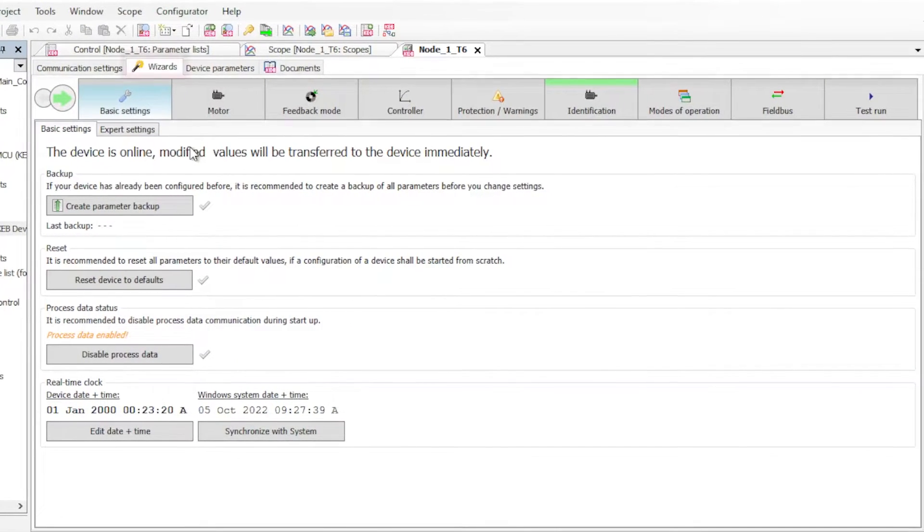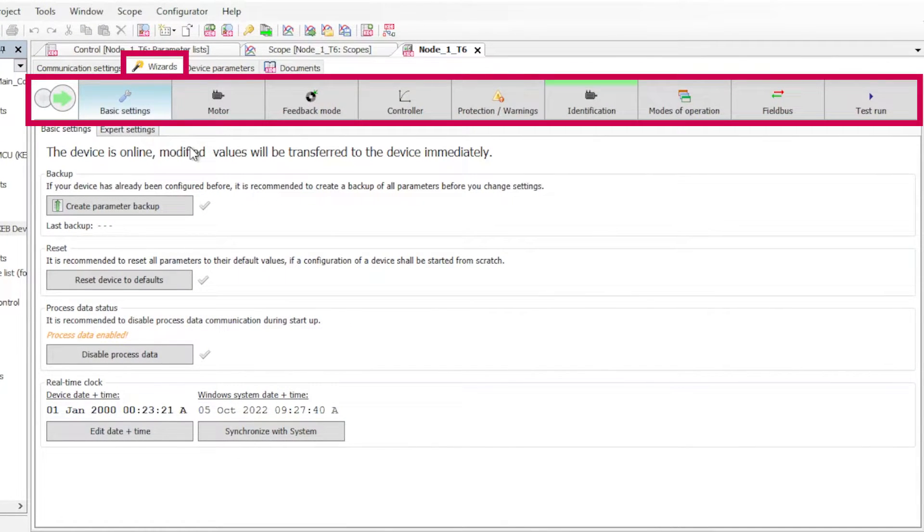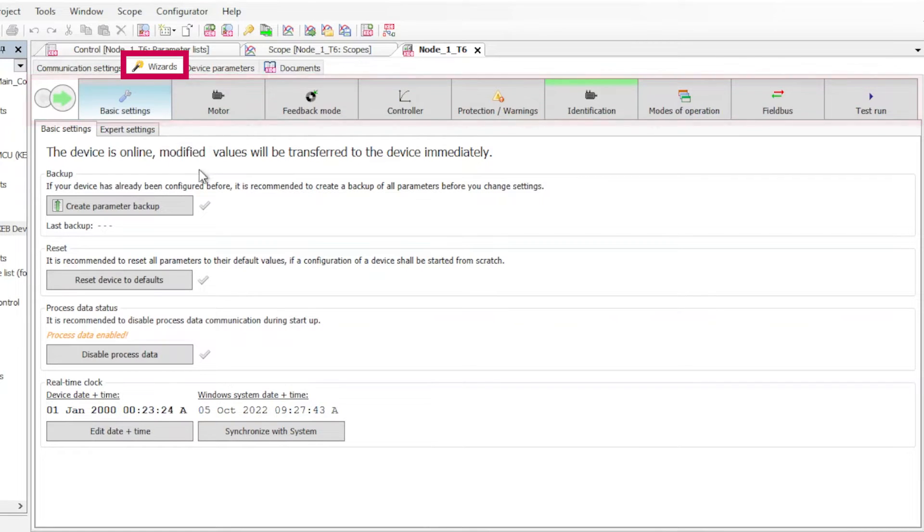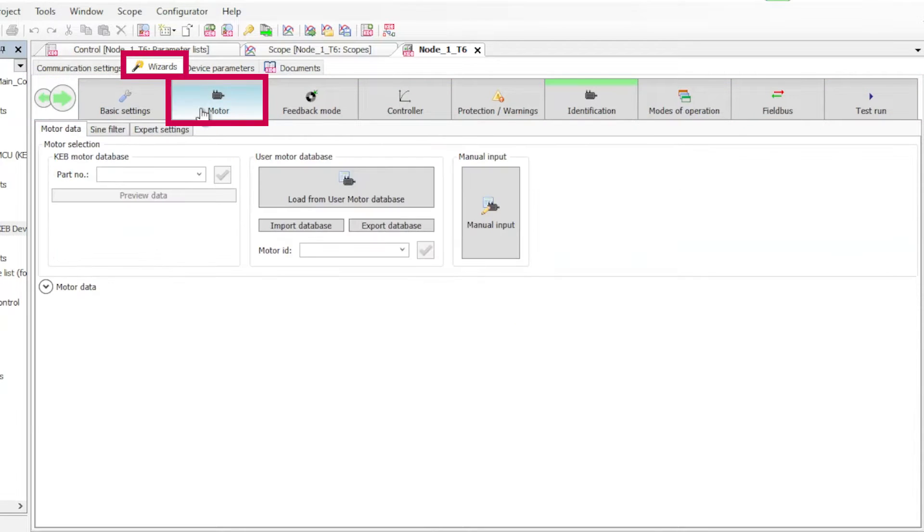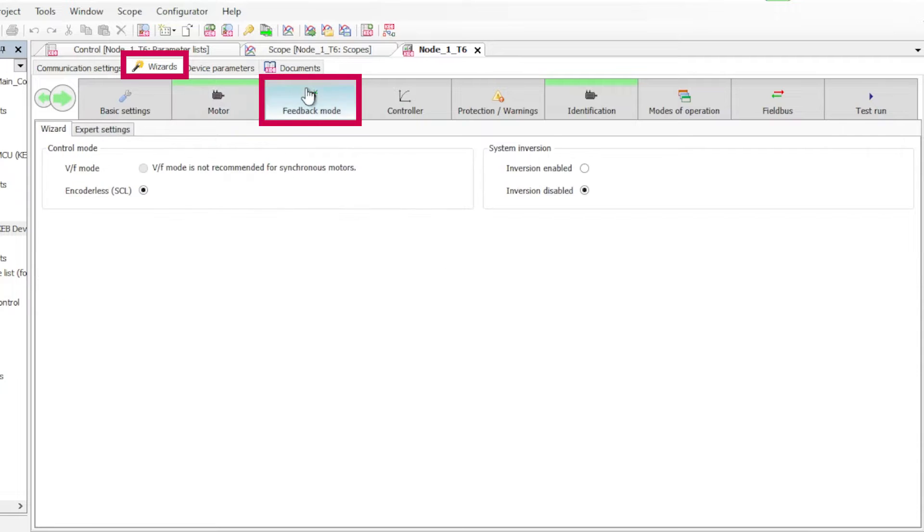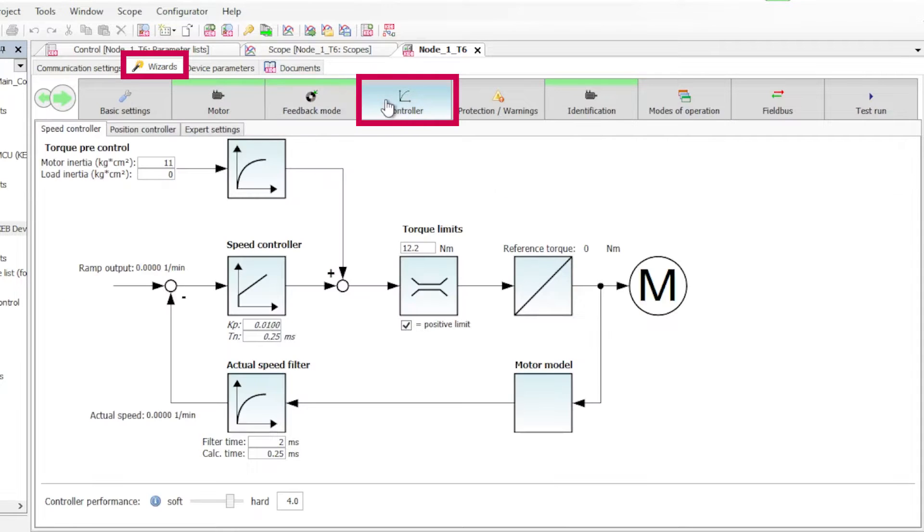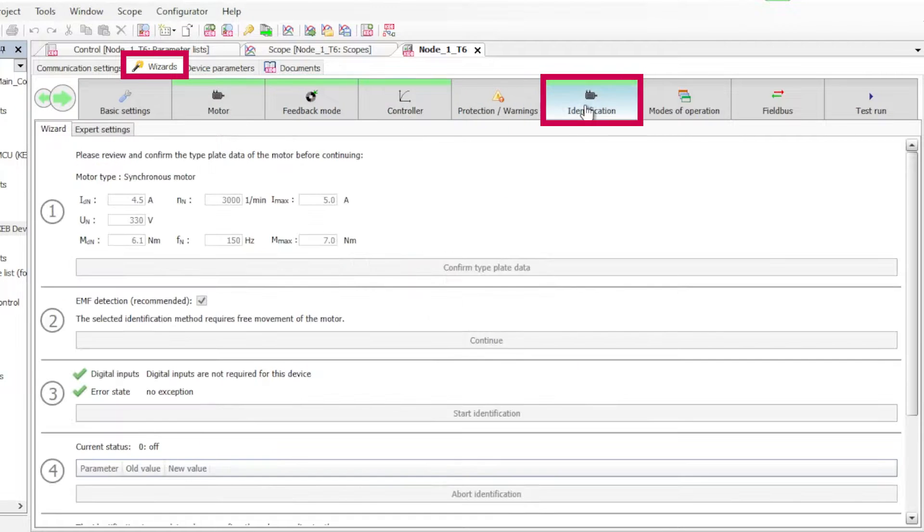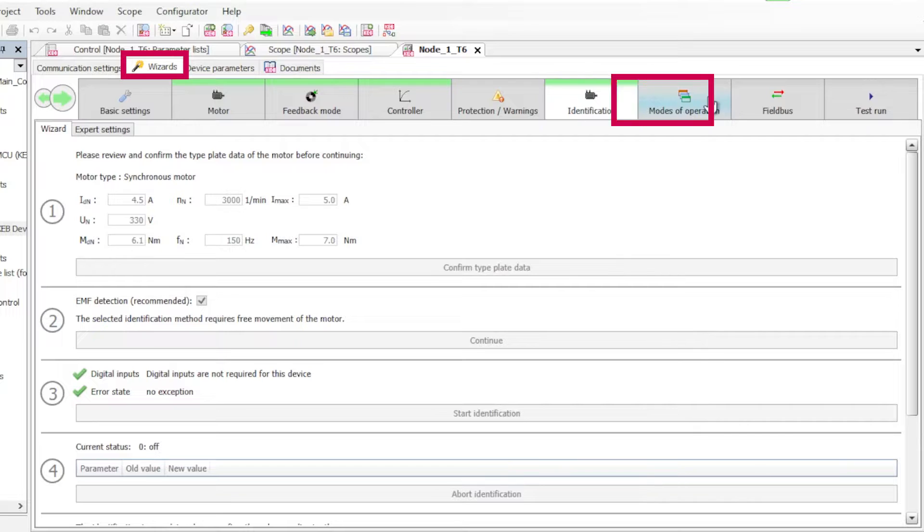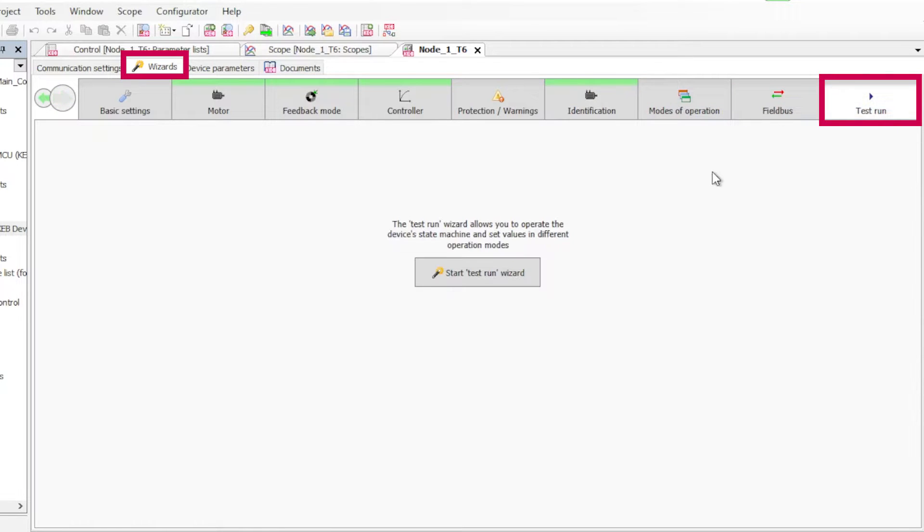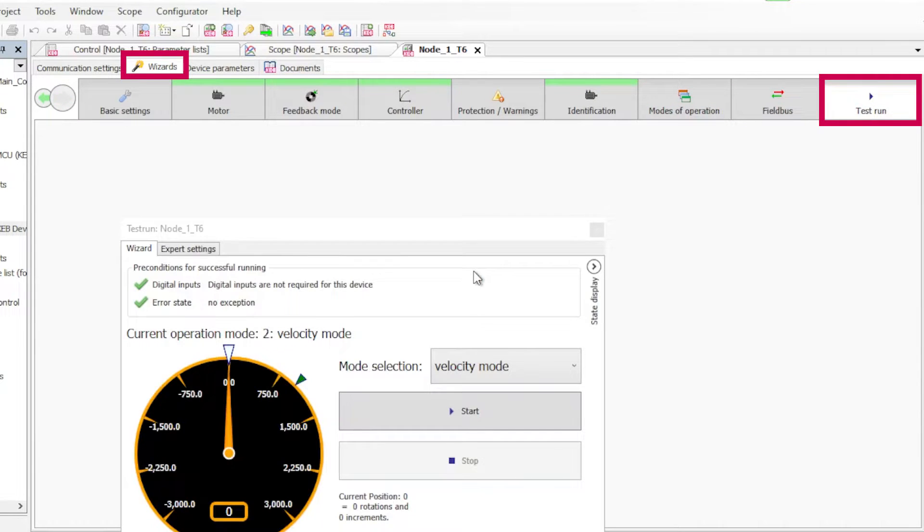COMBIVIS has simple startup wizards for getting your inverter paired with your motor very quickly. It has wizards for inputting simple nameplate data, choosing your feedback mode, choosing how the motor is controlled and also doing a motor learn. There's also a wizard for doing a test run to get your motor spinning even without field bus data.